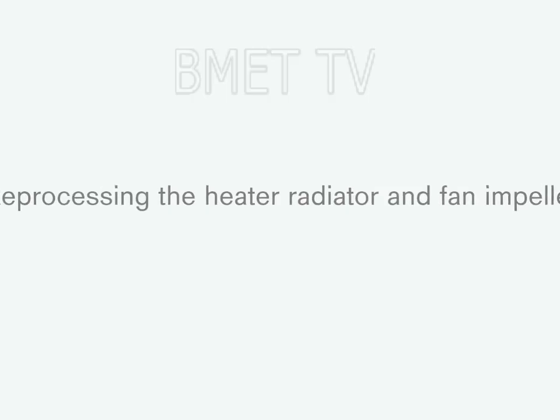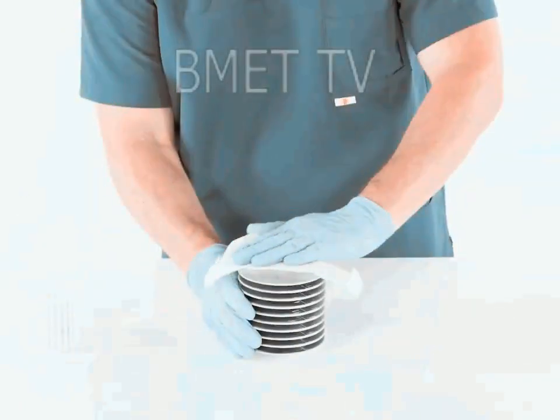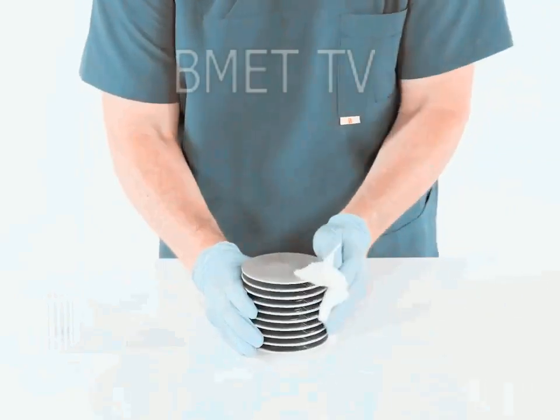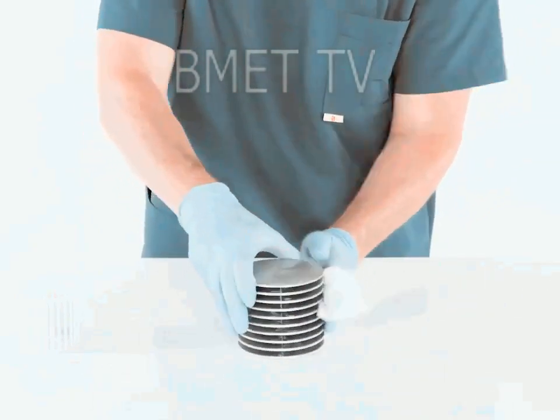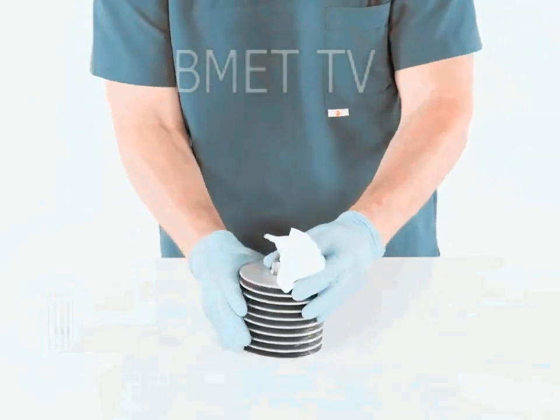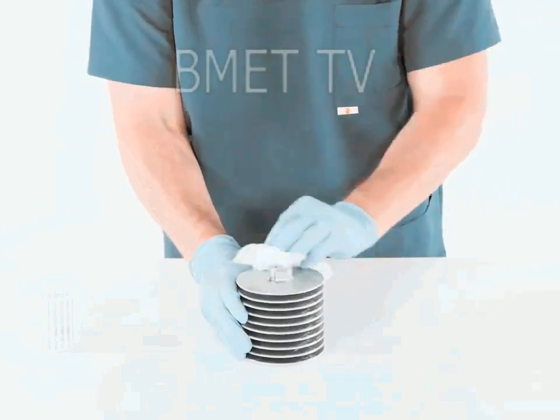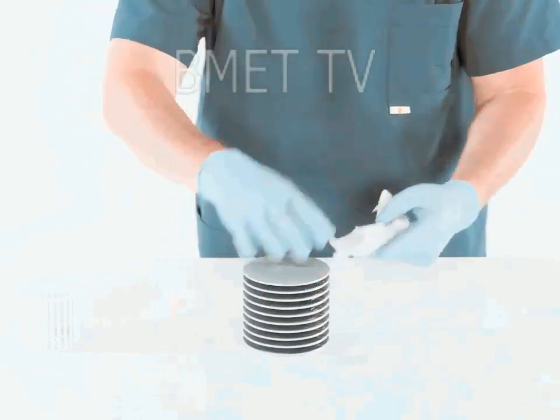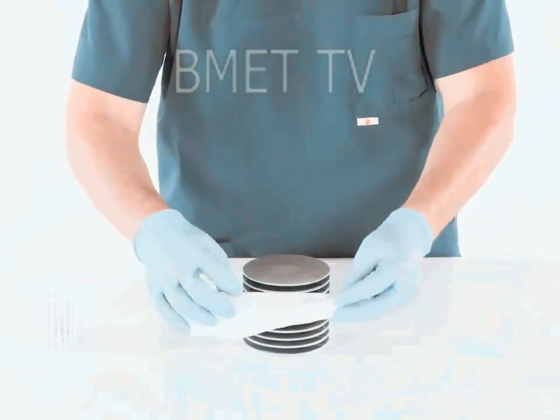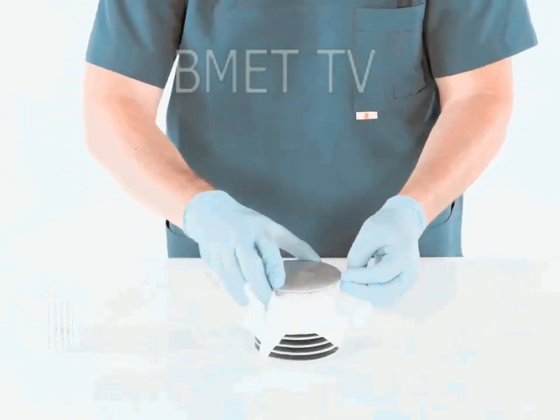The third component is the heater, a heating element made from coil resistance wire as known from hair dryers, or of the tube type, flat or coiled, as seen in autoclaves, used to heat up the air. But unlike in autoclaves, the heater has much less power and thus does not get so hot. The power rating is between 100 and 300 watts. The heater is controlled by an electronic temperature control unit via a relay or triac, or simply by a thermostat.